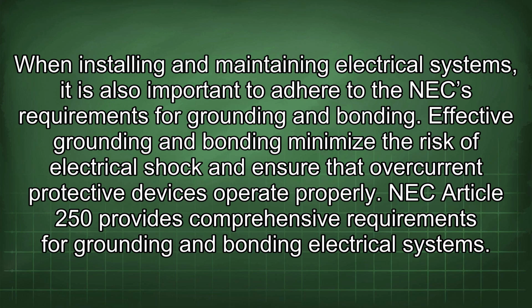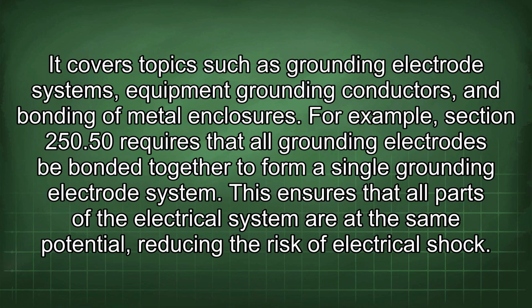When installing and maintaining electrical systems, it is also important to adhere to the NEC requirements for grounding and bonding. Effective grounding and bonding minimize the risk of electrical shock and ensure that overcurrent protective devices operate properly. NEC Article 250 provides comprehensive requirements for grounding and bonding electrical systems. It covers topics such as grounding electrode systems, equipment grounding conductors, and bonding of metal enclosures. For example, Section 250.50 requires that all grounding electrodes be bonded together to form a single grounding electrode system.